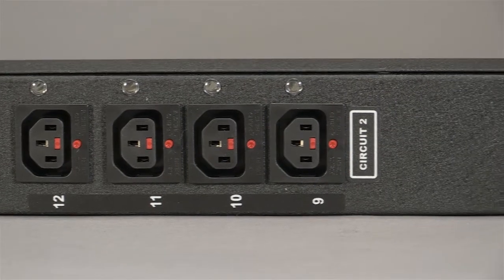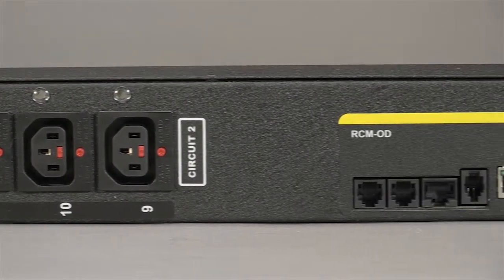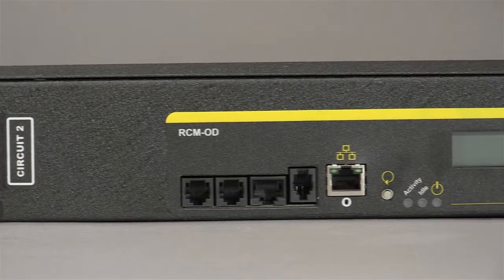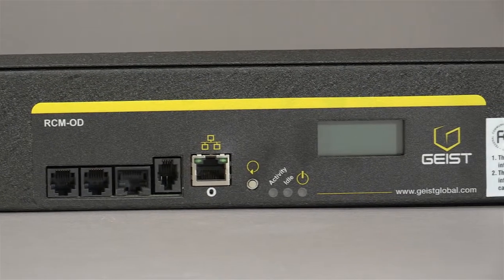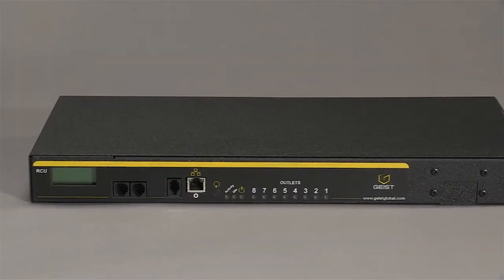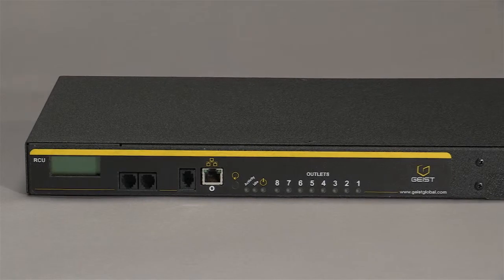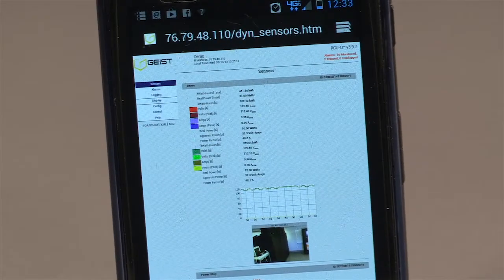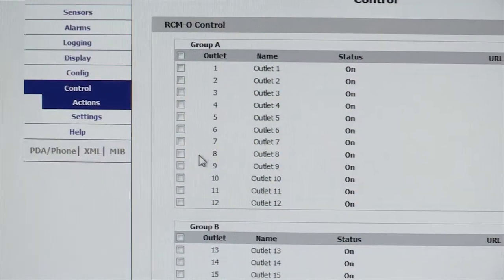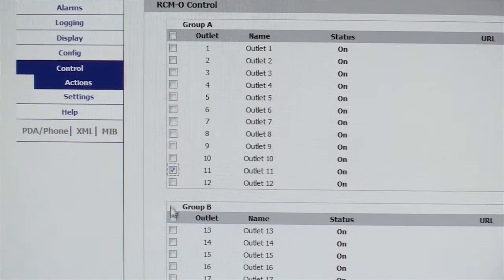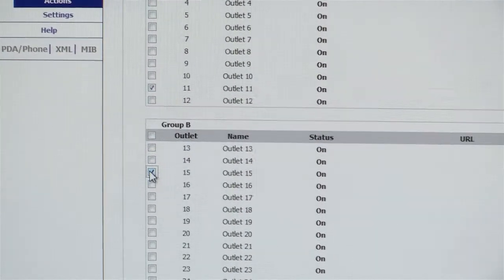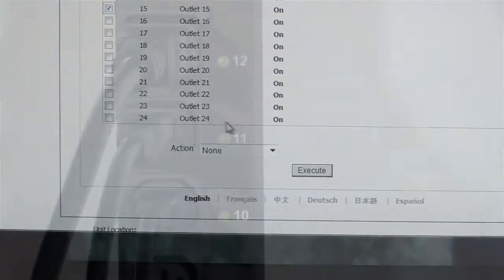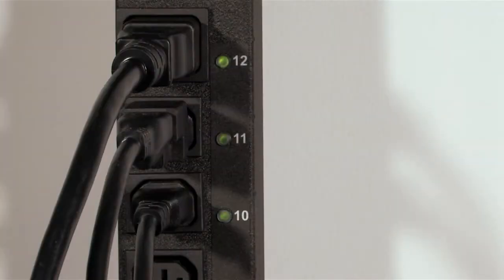Switched PDUs have all the features of monitored PDUs, with the added ability of controlling whether the outlets are in on or off mode. The IT manager can turn on or off any piece of equipment plugged into an outlet of a switched PDU from any location with web access. He can reset stalled equipment by remotely cycling the power, and by turning off unused outlets, he can safeguard against unauthorized power connections that could overload the system.